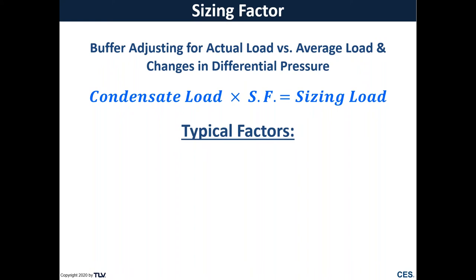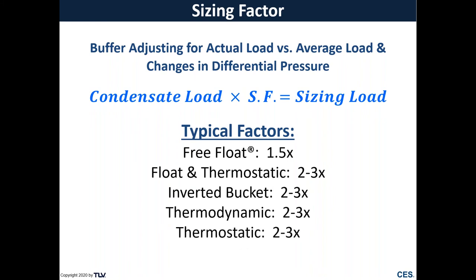So typical sizing factors we see for something like a TLV free float would be a 1.5 times sizing factor. So for a steam application with a 1,000-pound condensate load, we'd want to size that trap for at least 1,500 pounds an hour. And for other steam trap types, we're typically going to see about a 2 to 3 times sizing factor applied. But an important note here is that this is going to vary greatly based on the manufacturer as well as your site specifications. So we'd encourage you to look at your site specifications to determine if you have a specific sizing factor that you're required to meet, or if your manufacturer recommends something much larger.